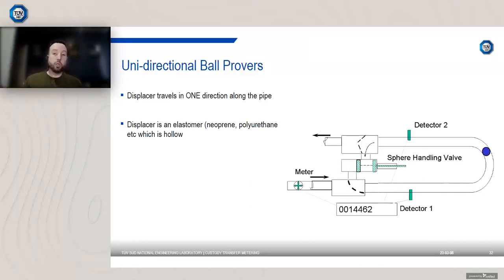The displacer is usually released into the flow using a special valve. The displacer triggers the first detector switch. You count the pulses, and then when you hit the second detector switch, you stop counting pulses. You know the volume between the detector switches, and that's how you can determine a meter factor.